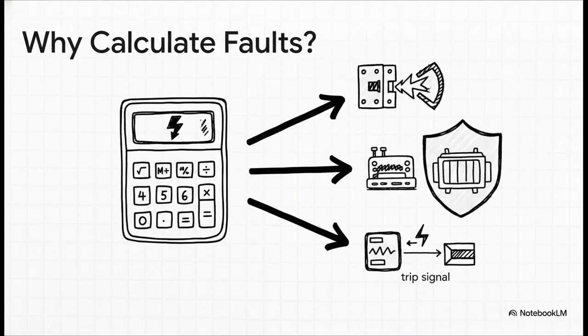Here's exactly why that calculation is so vital. The results of a fault study directly influence the design of the grid's safety systems. Engineers use it to pick out circuit breakers strong enough to interrupt those immense currents, to make sure expensive gear like generators and transformers won't burn out, and to set up the protective relays that detect a fault and isolate it in milliseconds.